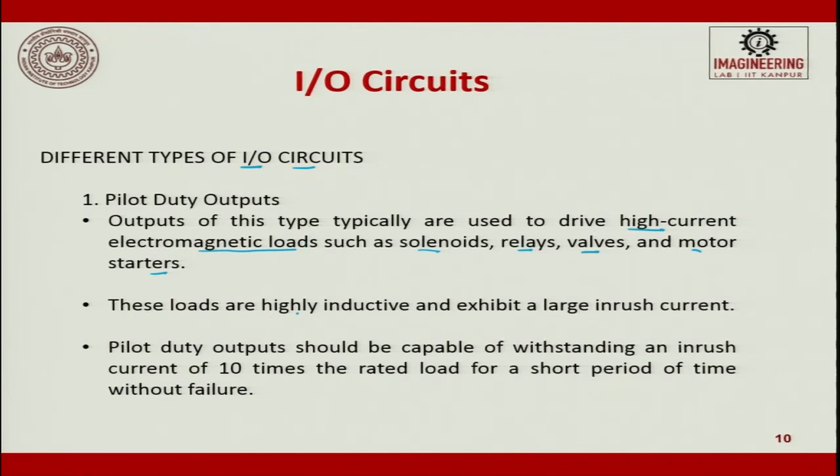These loads are highly inductive and exhibit a large inrush current, a sudden current. Pilot duty outputs should be capable of withstanding an inrush current of 10 times the rated load for a short period of time without failure.